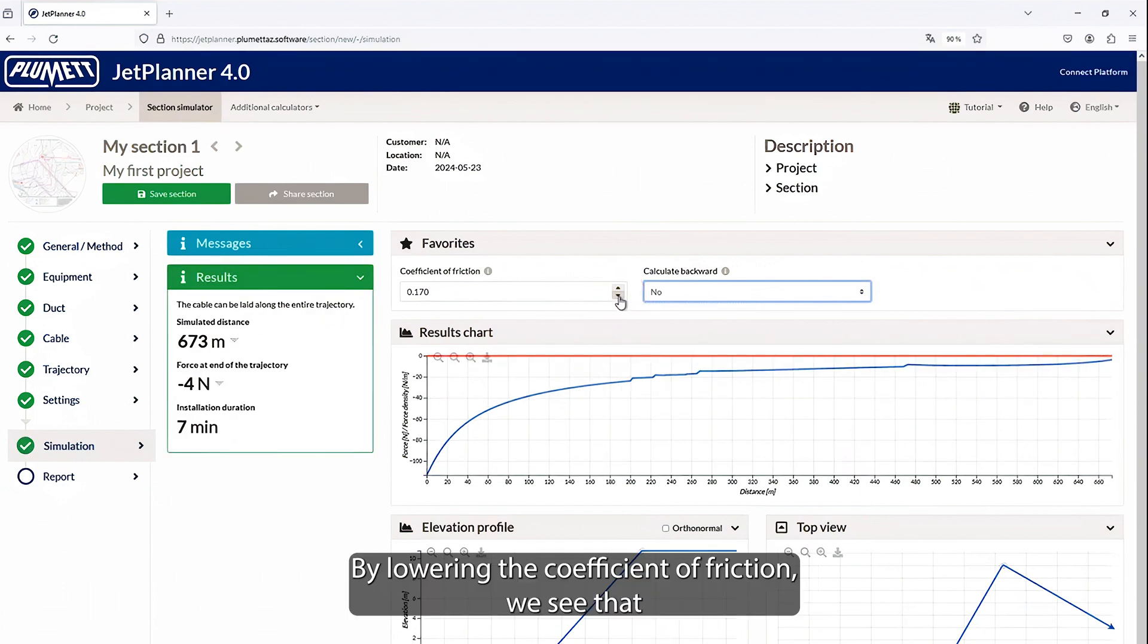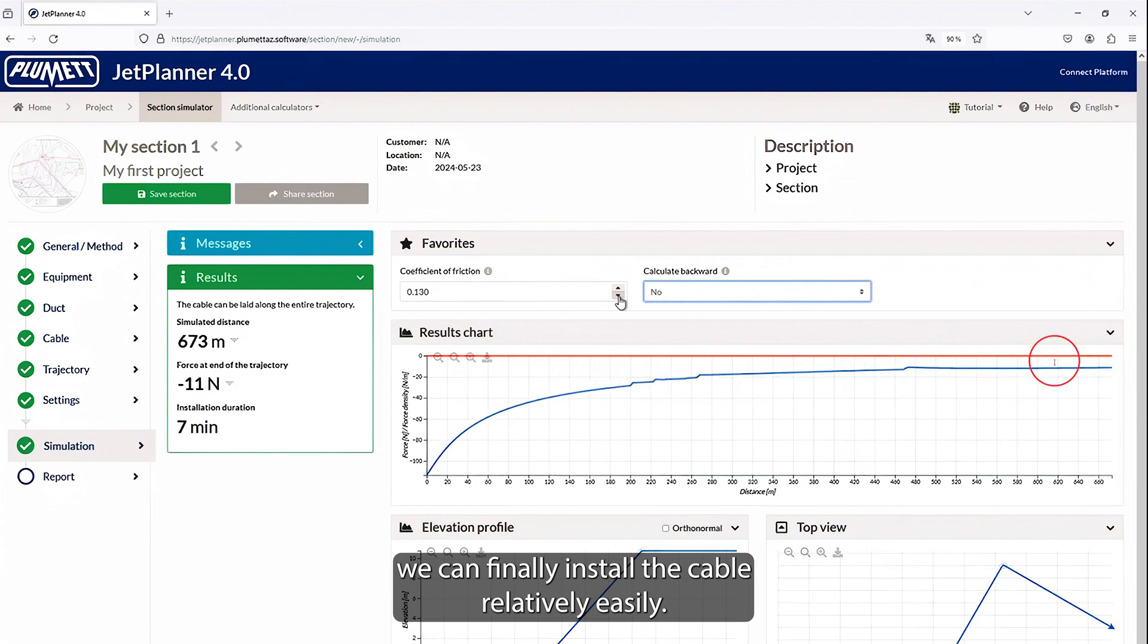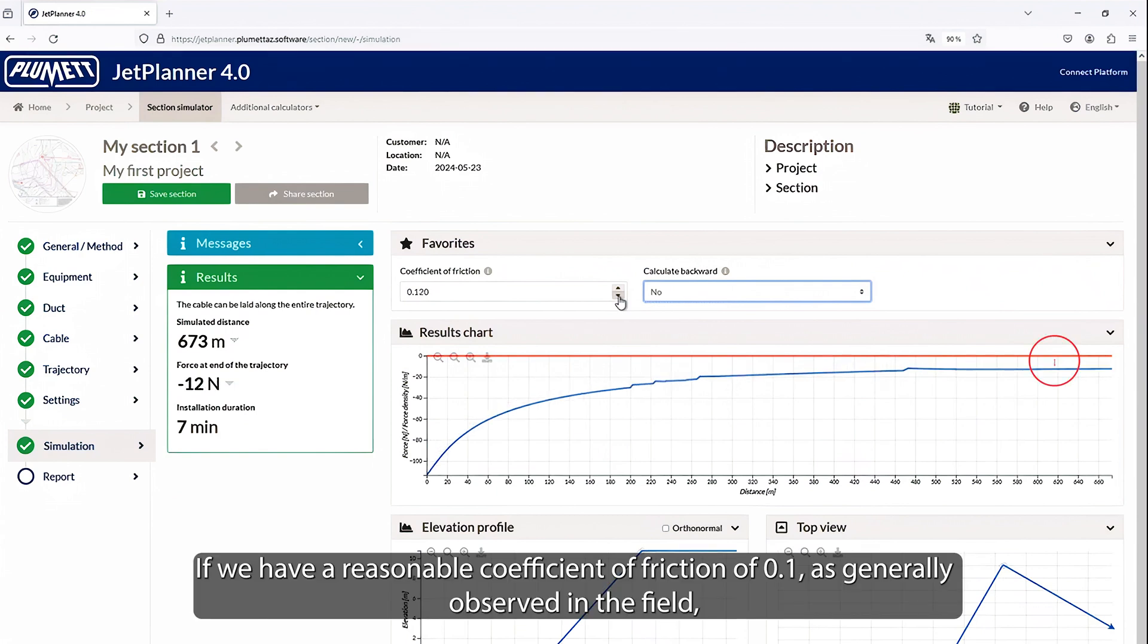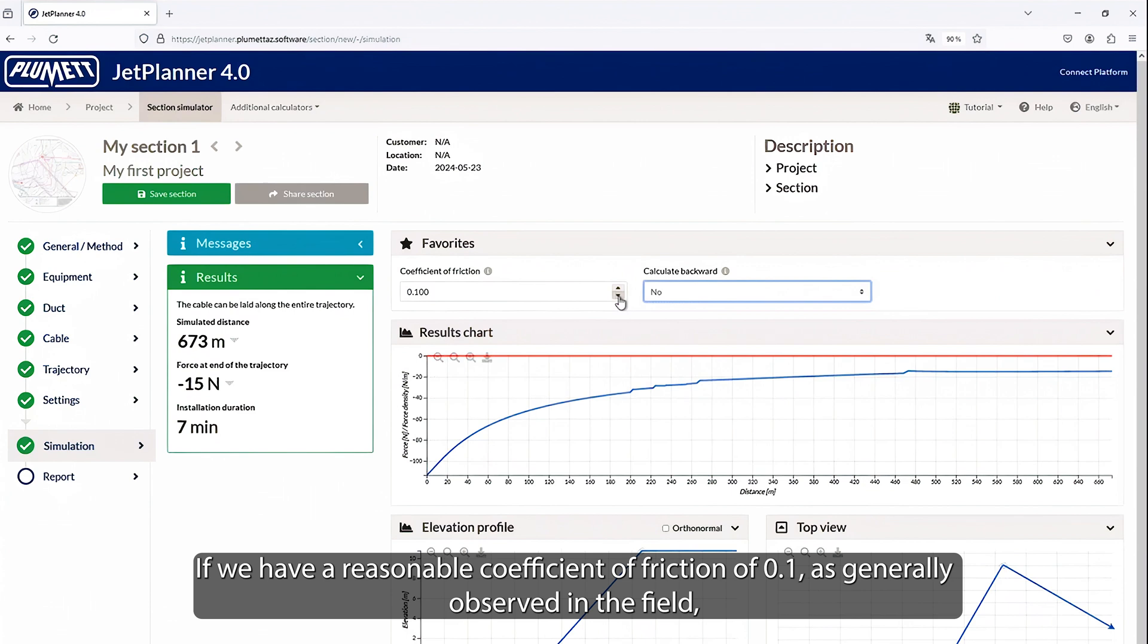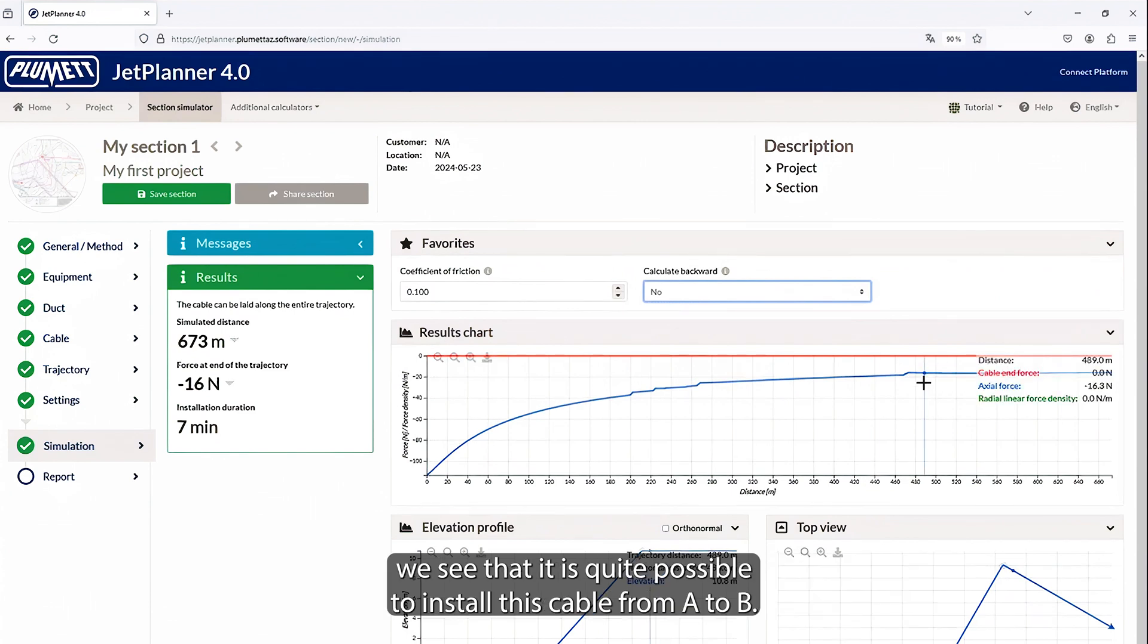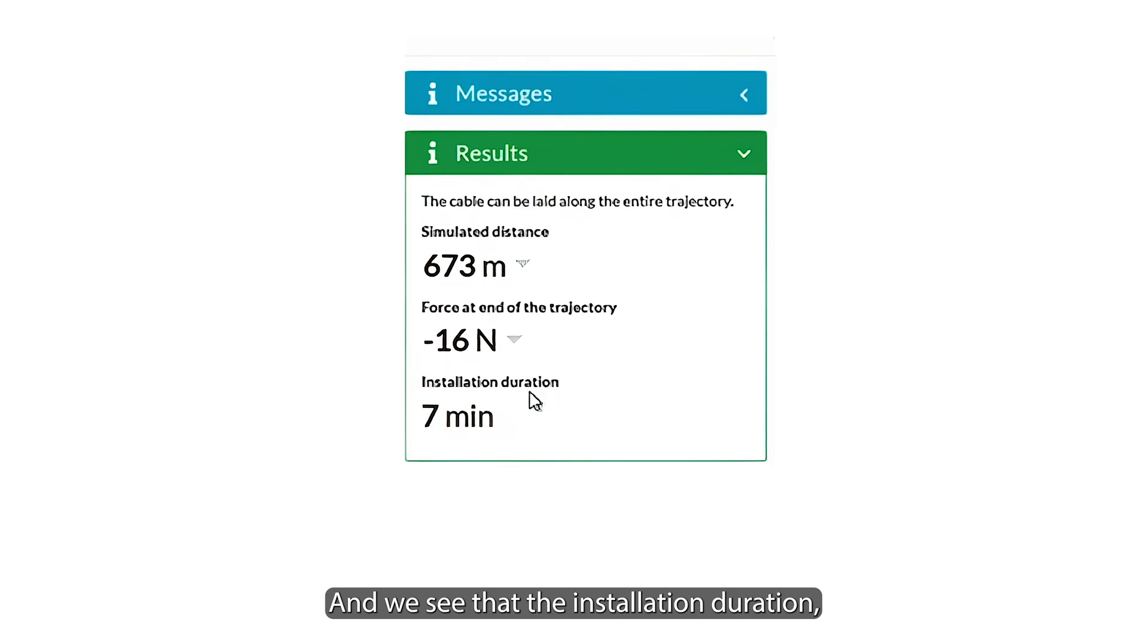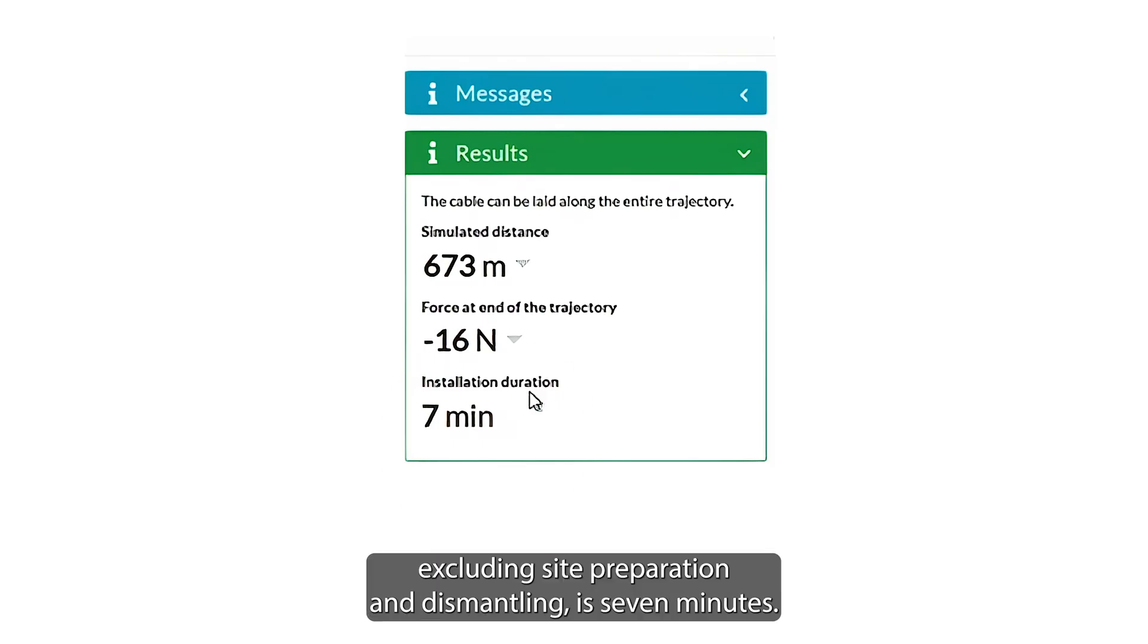By lowering the coefficient of friction, we see that we can finally install the cable relatively easily. Similarly, if we have a reasonable coefficient of friction of 0.1, as generally observed in the field, we see that it is quite possible to install this cable from A to B. And we see that the installation duration, excluding site preparation and dismantling, is 7 minutes.